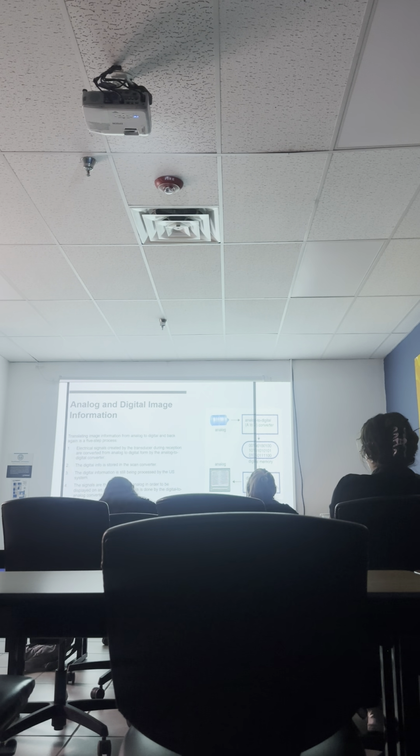The signals created by the transducer during reception, which means the echoes, are converted from analog to digital by the analog to digital converter. The digital information is stored in the scan converter. Then the digital information is processed by the ultrasound system. These signals are then turned into analog in order to be displayed on an analog display. This is done by the digital to analog converter. The signal, now in analog form, is presented on the analog video display.